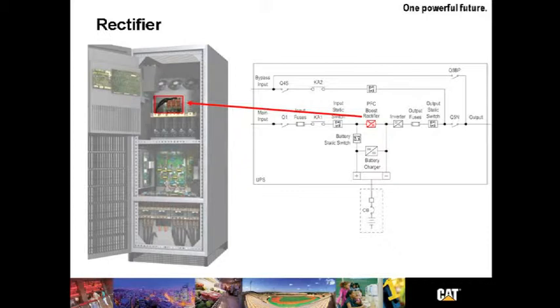The chopping frequency is fixed at 5,000 Hertz. Chopping is the frequency that the rectifier chops or cuts the incoming sine wave. This rectifier utilizes six fully controlled IGBTs that are protected by ultra-fast fuses.